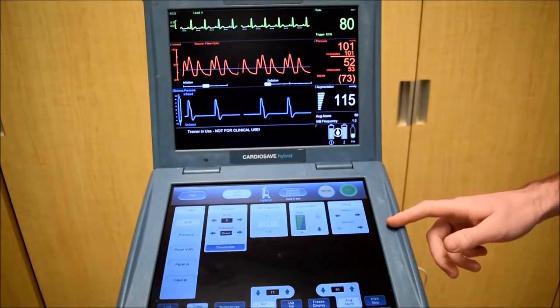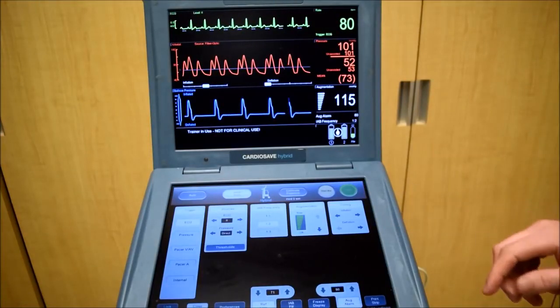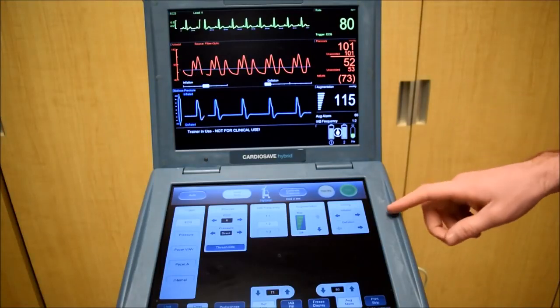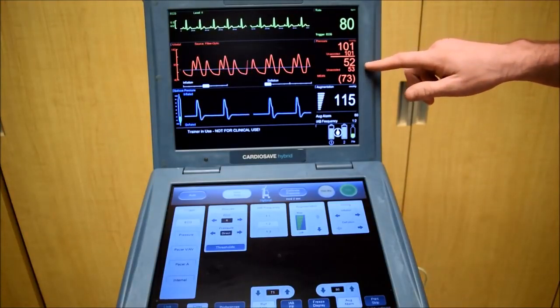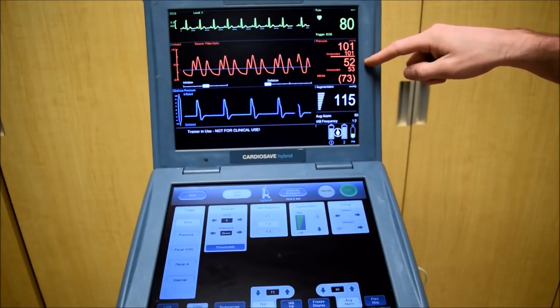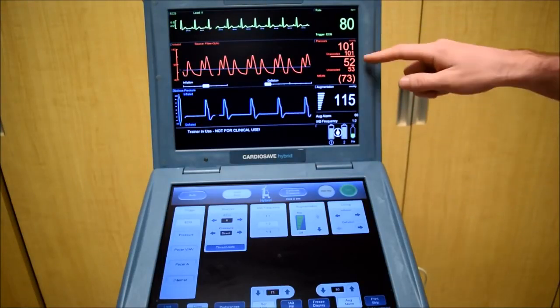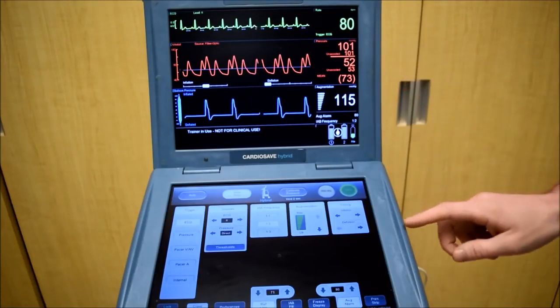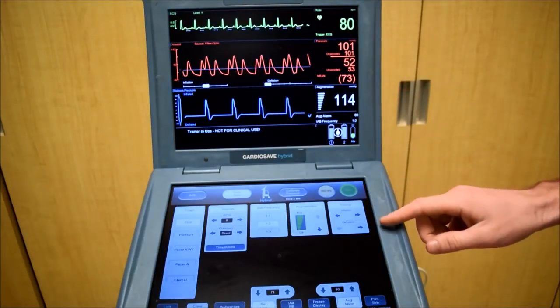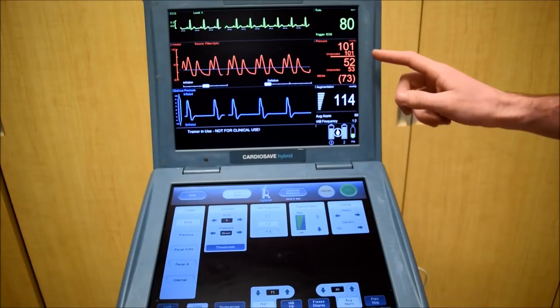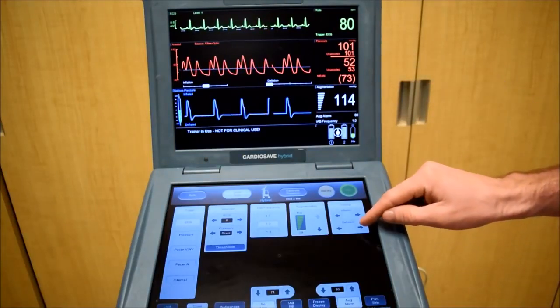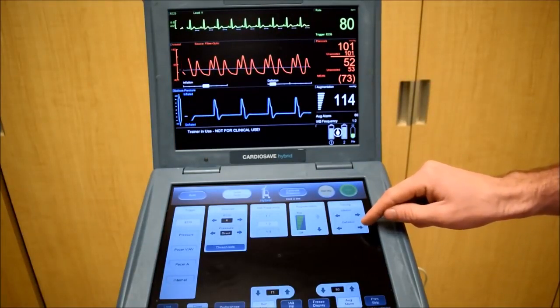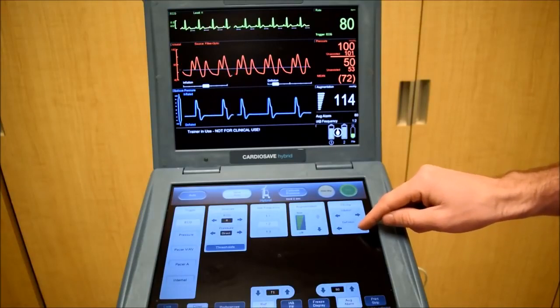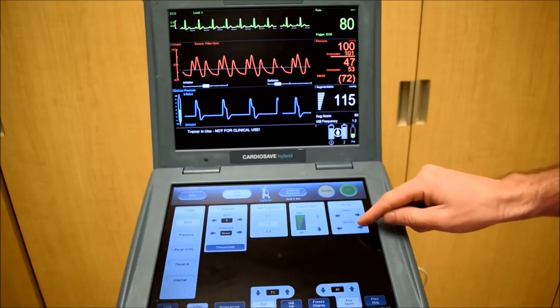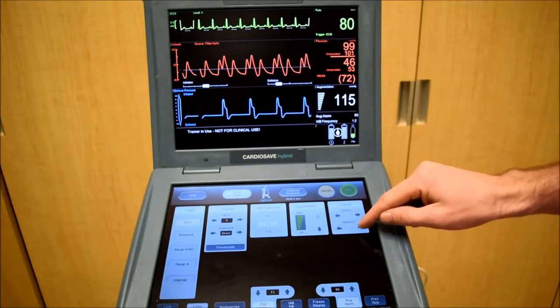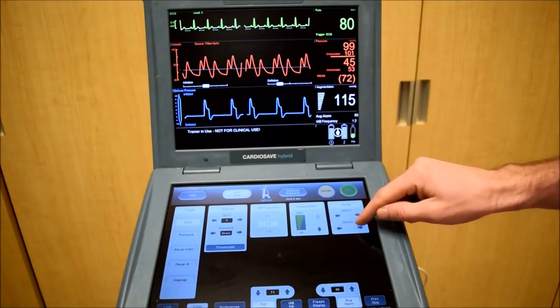Okay, now let's adjust our deflation. The optimal point for our deflation timing is to get the lowest assisted diastolic pressure. Right now we're at 52. I'm going to move this deflation timing later, and we should see this drop. Alright, now we're at 50, 51, 47. Okay, we're really getting down there.